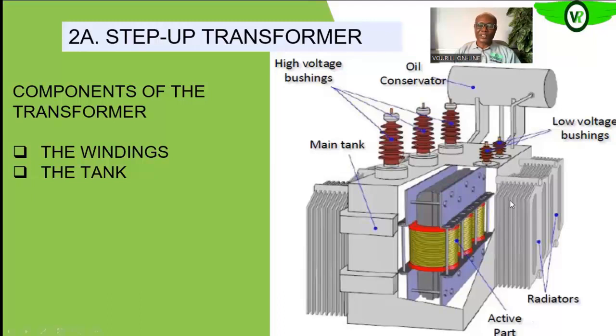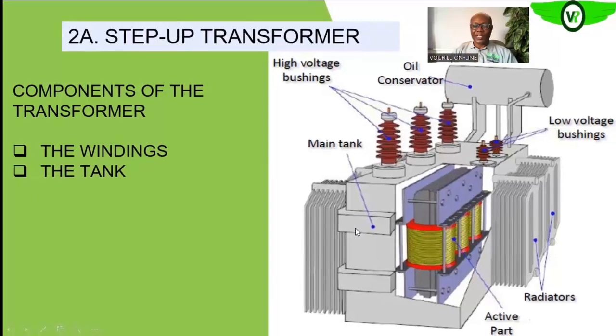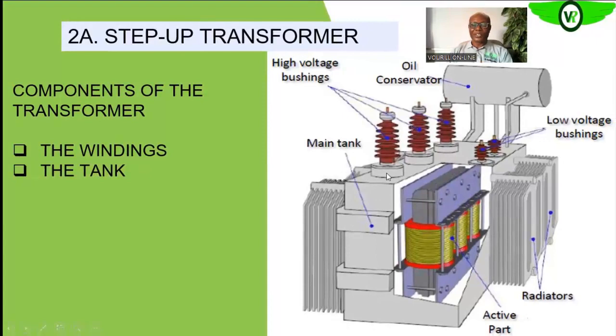So the tank also, as you can see, carries all other components, both protective and those needed for the transformer to function properly, like the bushings. They are on the tank. The conservator is on the tank also. Even the radiators, the cooling fins, and what have you, are all attached to the transformer tank. So we also have another very important section of the transformer, which is the cooling system.